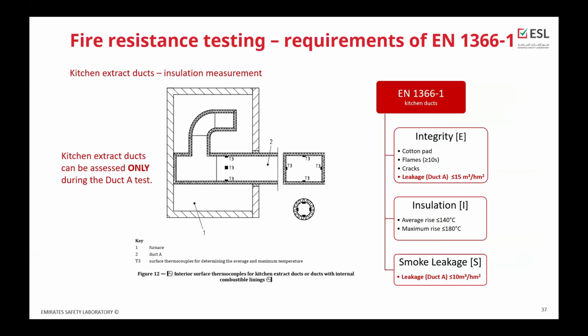Also, the European standard prescribes precisely where to put thermocouples inside the furnace, inside the duct A, to assess kitchen extract duct. BS just tells us that we need to measure the temperature if you want to get the kitchen extract duct, and this temperature cannot exceed the limits. However, BS does not state where and how to put them. EN tells us exactly where and how to put thermocouples and provides much more detail. However, for both BS and EN, kitchen extract duct can be assessed only during the duct A test. You cannot get the classification and the certificate for the kitchen extract duct having only a duct B test, because there are no thermocouples inside the duct for assessment of the kitchen extract duct.